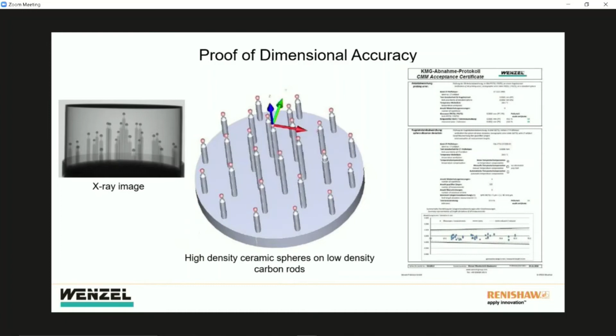Okay, and the next step is we scan it in the CT. Then on the right-hand side we can display a graph that shows, over the lengths, the difference between our well-known accurate values from the tactile CMM and the values from the CT. So this is a way to prove the dimensional accuracy of a CT.